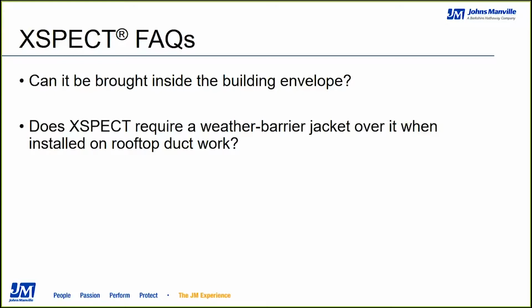And again, that is why the product ends up externally more often than not, because a local code body will potentially make an exception to those 25/50 rating codes on an exterior application and allow it to be used outside. Does X-Spect require a weather barrier jacket over it when installed on a rooftop duct? And the answer to that is yes. There is a need for a weather barrier, and there are a number of different jacket styles available, and they're typically also used for sealing up the system for a vapor barrier as well.